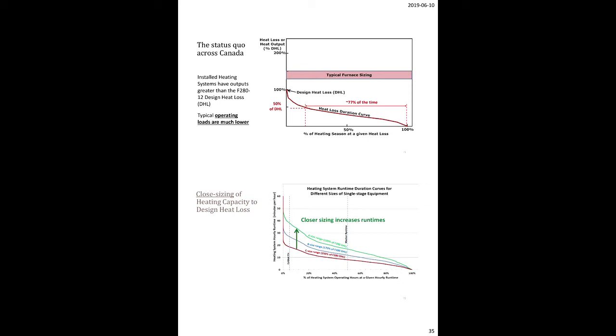What's the smallest single-stage builder-grade furnace on the market? It's about a 40, 39,000 output. So now our load is effectively half that. If we put in the standard smallest single-stage unit, we've oversized it.